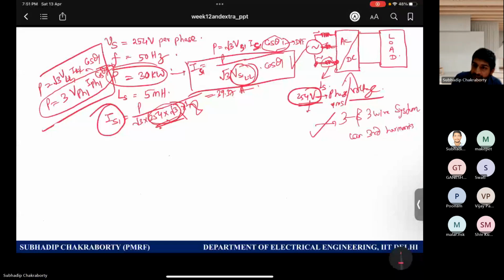From which parameter can I determine the amplitude or strength of the harmonic currents in the phase? From the harmonic voltages, right? Yes, sir. 11th harmonic voltage. Well, yes. Please be interactive. The harmonic voltages will only give me the information about the harmonic currents.